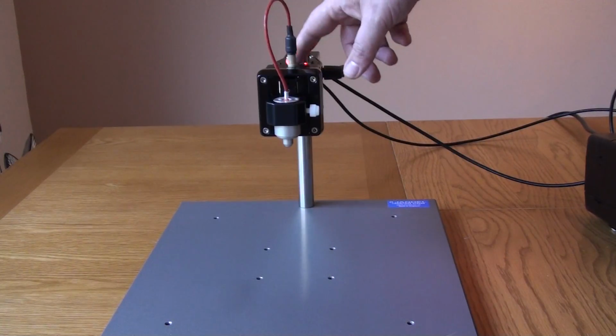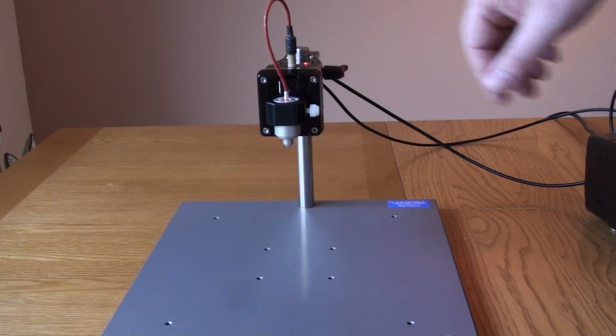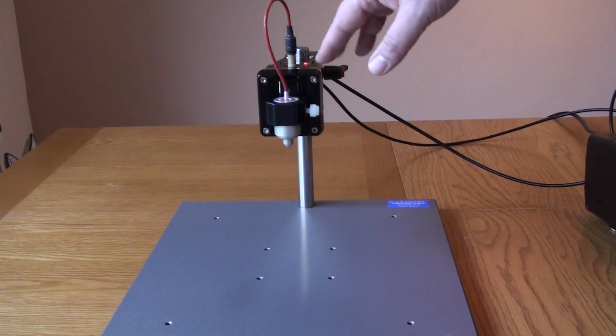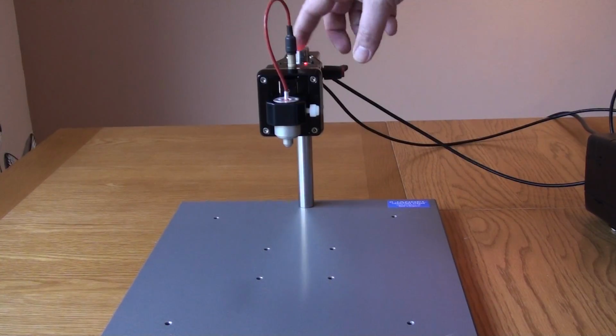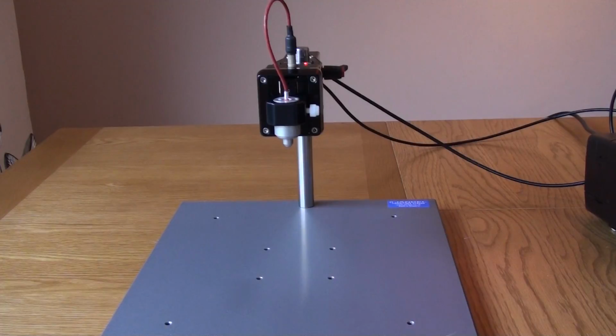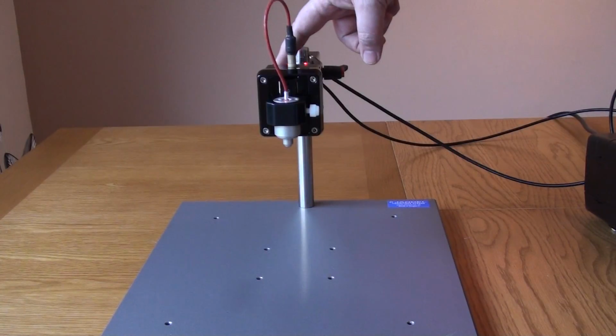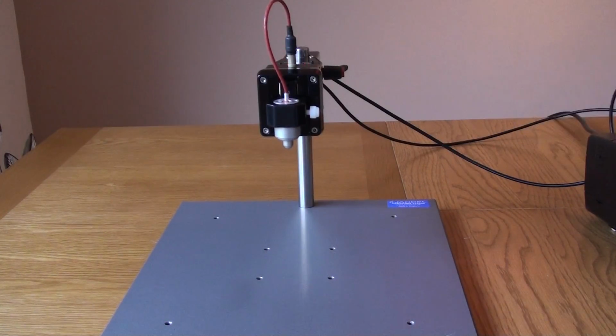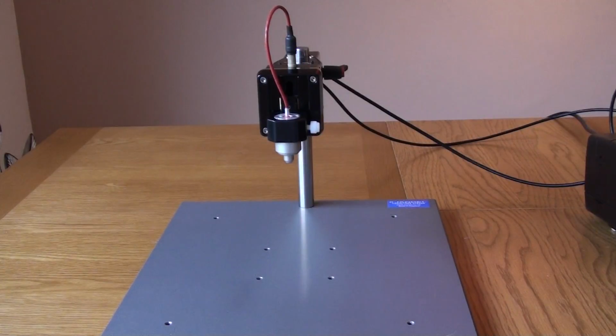We then change the needle load to match the needle load on the probe head. In this case I'm using a 100 gram probe, and so I've changed the needle load to 100 grams. Press and hold the needle load button and the probe head holder will move to its lowest position.